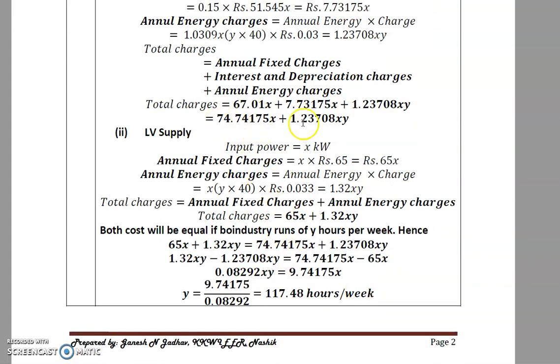Equating the total charges of HV and LV supply to find y: solving the equation gives y = 117.48 hours per week. If the industry works more than 117.48 hours per week, HV supply is cheaper; below this, LV supply is cheaper.